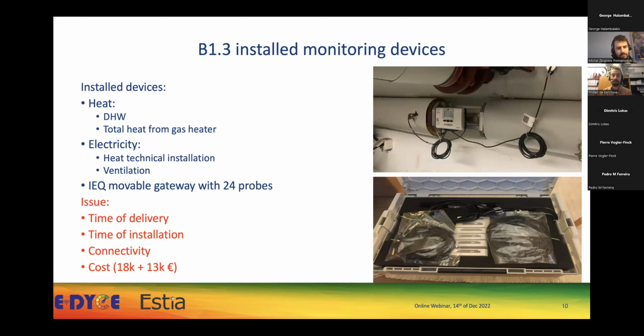We also installed counters for electricity to get the consumption of the heat technical installation as well as the ventilation, because in this case we changed the ventilation system at one point and wanted to see the improvement. Also, to follow the quality of the indoor environment, we installed a movable gateway with 24 probes connected, placed in the different rooms of the building.